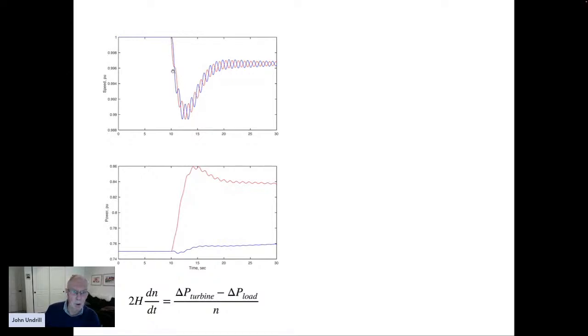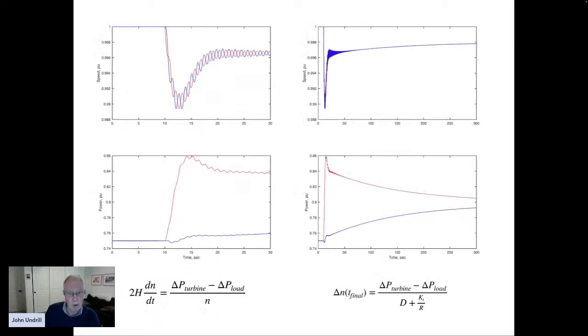The speeds are a little bit different from each other as the whole connection of generators jiggles around a little bit. I call this the sizzle of speed. The speed of the machine goes from here down to here and then follows to here with a sizzle superimposed on it. Here's the same graph as we saw before. Well, that's not the whole picture. Here's the whole picture.